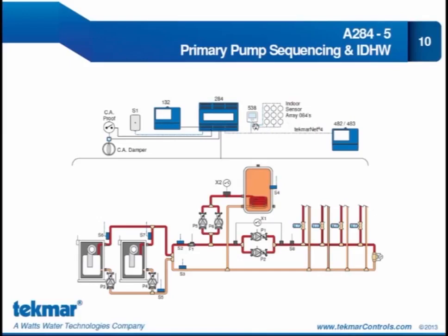Now those indoor sensors can be connected to the 538 tekmarNet 4 thermostat using series parallel wiring. And because we're using series parallel wiring, it has to be a perfect square number. So we could use 4 sensors. The next number we could use would be 9, and the next number we could use after that would be 16. So these sensors are going to provide indoor temperature feedback that will fine-tune the boiler supply temperature from that outdoor reset temperature. And what that's going to do is save energy by operating the heating plant efficiently and prevent tenants from opening the windows because they're too hot. S8 here is a pressure sensor. Now the pressure sensor is another new feature for the 284, and it allows us to monitor the pressure in the system. We'll talk about that pressure sensor more later in the presentation.